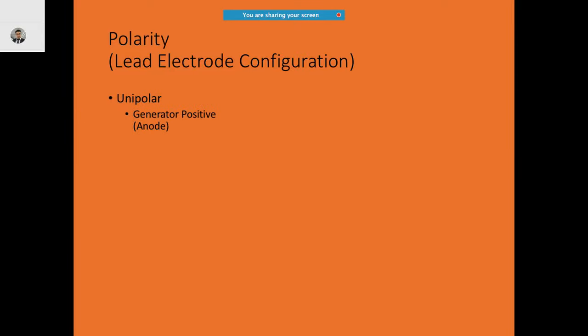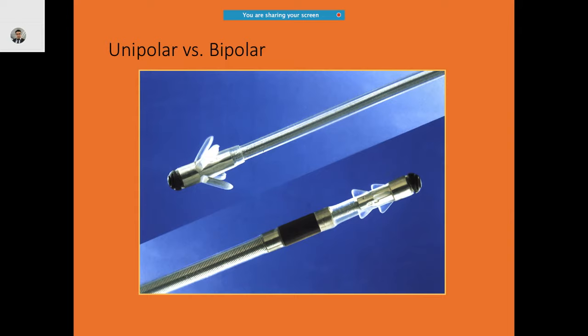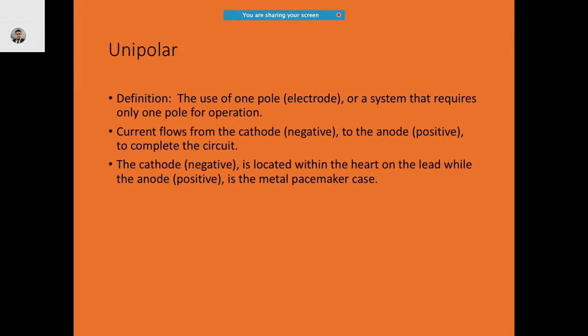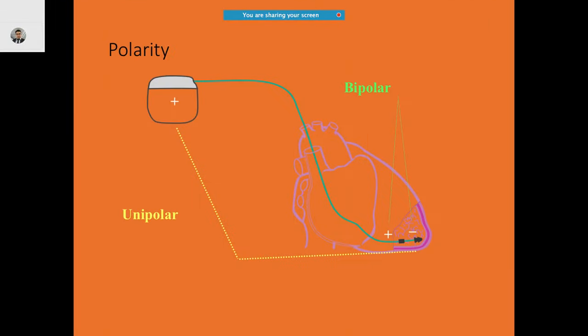Leads can be unipolar or bipolar. If it is bipolar, the lead ring is the anode, meaning it is positive, and the lead tip is the cathode, meaning it is negative. So the tip is negative and the ring is positive — that makes it bipolar. On a normal basis, the tip is always negative whether it is a unipolar or bipolar configuration.